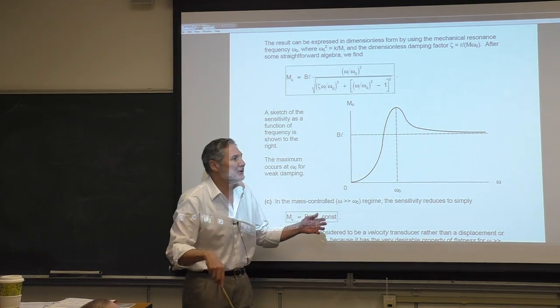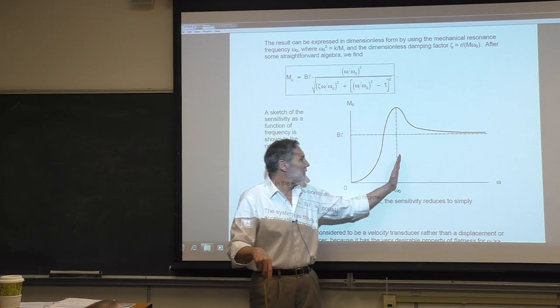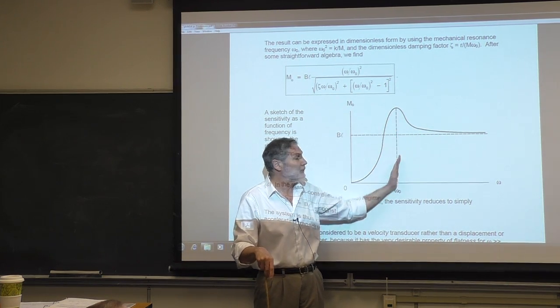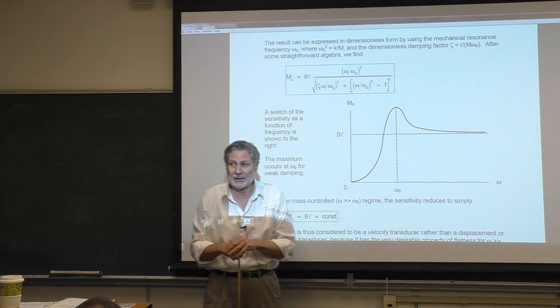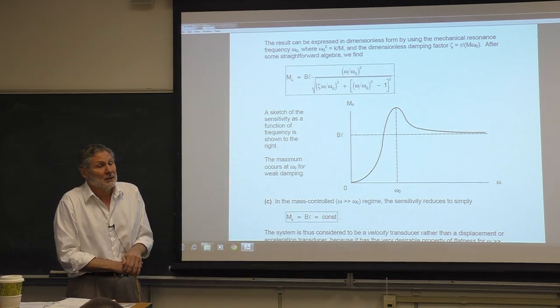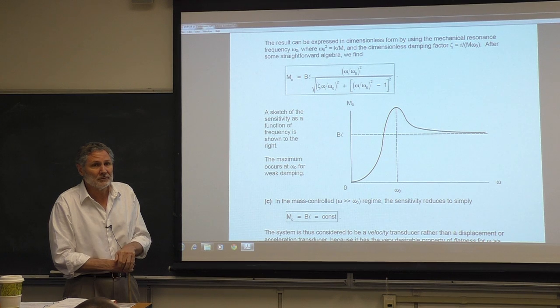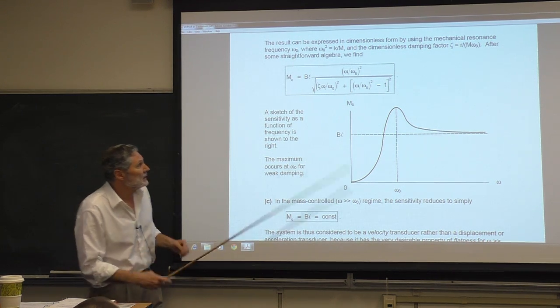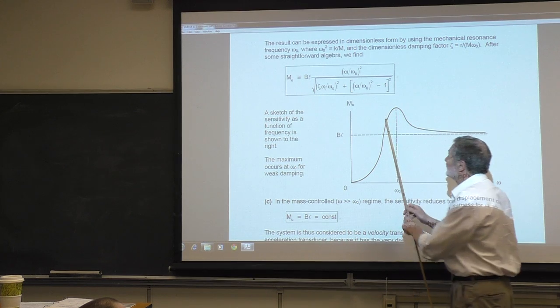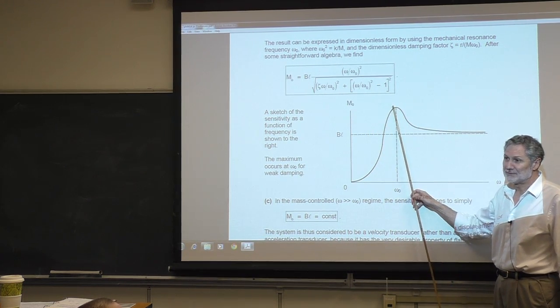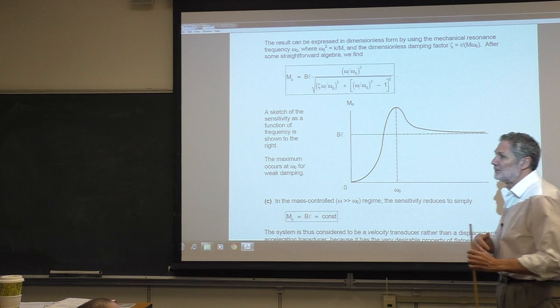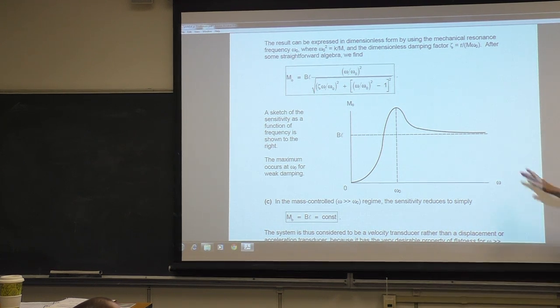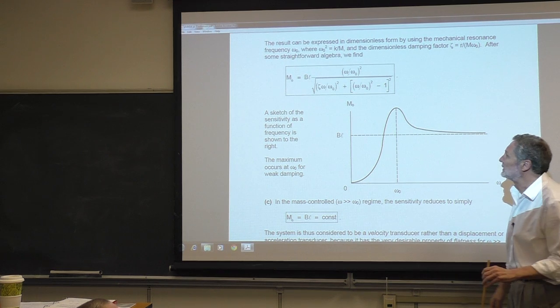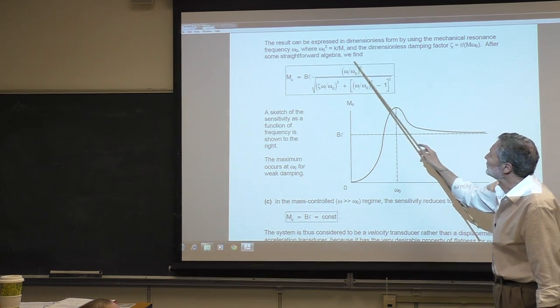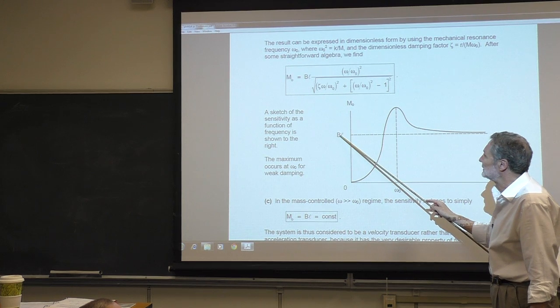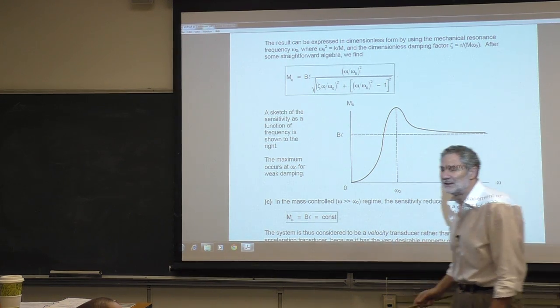Now, of course, in your particular application, you may want to operate right here, but you're just going to have to be careful. You may want to operate on resonance. You may be building something you intentionally will operate on resonance for whatever reason. Maybe you want to just get the maximum response. Maybe you've got noise problems. You're just going to have to make sure you use the appropriate sensitivity, right? But typical for broadband application, you're going to operate over here. And the sensitivity is what? Well, we decided this was 1 asymptotically for large omega, so the sensitivity is just B times r.